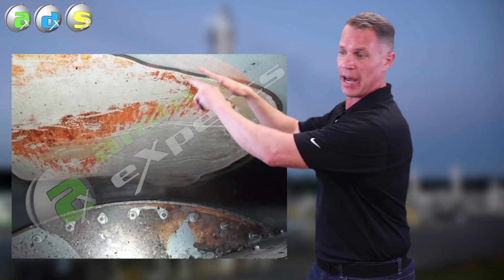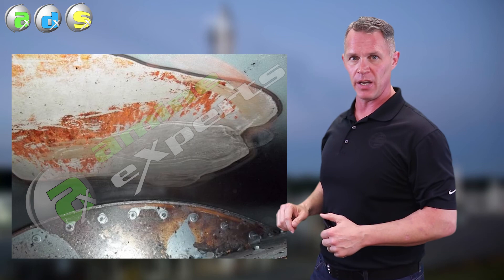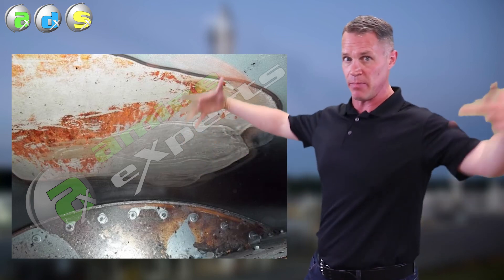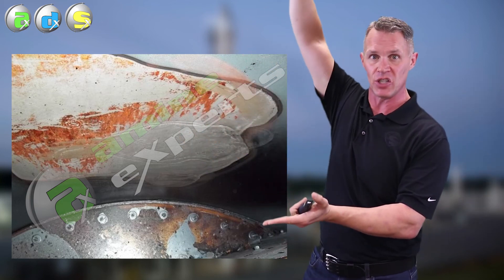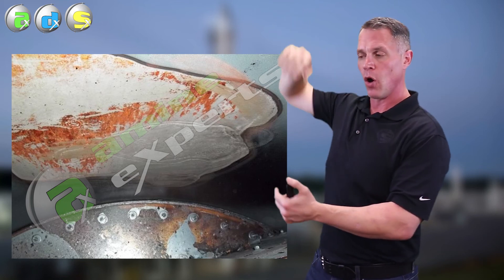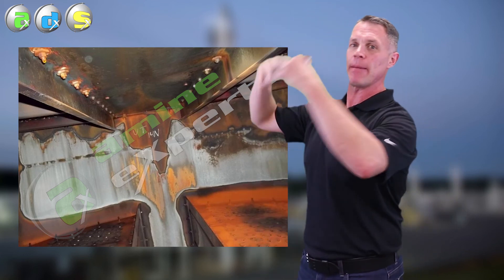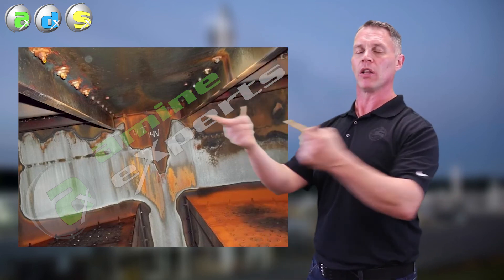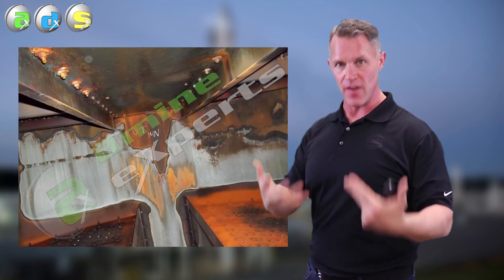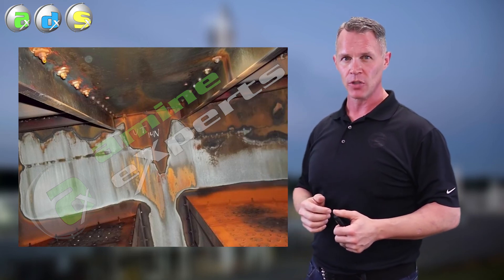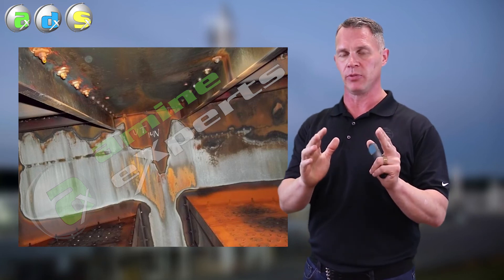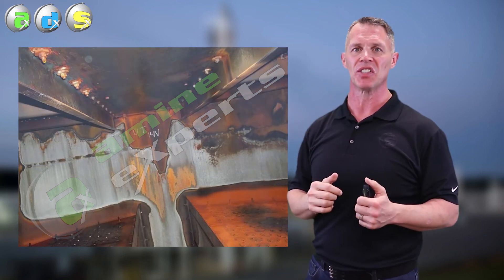Hydraulic effects can also cause corrosion. So here's a case where we had low downcomer flooding. So they just weren't circulating enough amine. Big downcomer, low amine. So a lot of the downcomer was again, just bare, bare metal. Or in another example where we had low vapor flooding or low jet flooding, not enough steam to splash the amine up around the wall of the vessel. And so again, bare metal, very prone to CO2 attack. So be very careful if you're trying to operate your plant different than what it was designed for. Because you may be setting yourself up for failure from a hydraulic point of view.